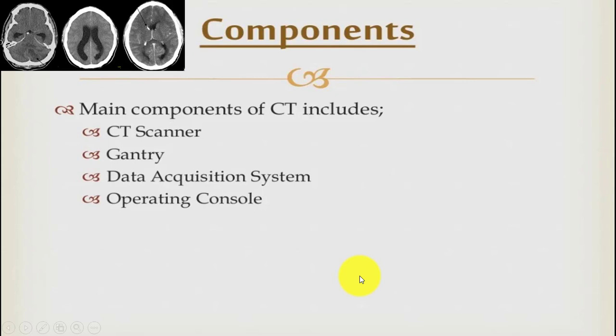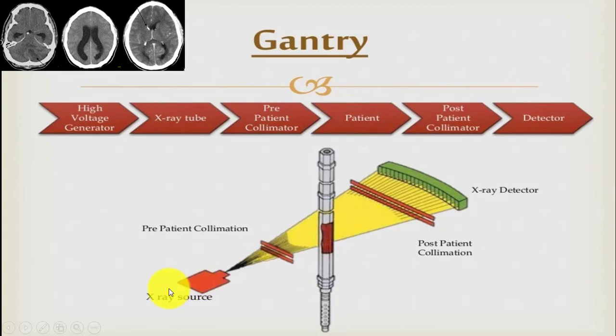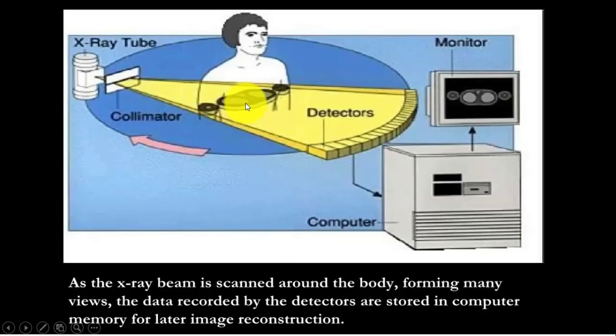In the CT scan system, high voltage generates x-rays which then pass through the x-ray tube, then pre-patient collimation, then patient scanning, then post-patient collimation, and ultimately reach the detectors. Here is a visual animation of the CT scan showing the x-ray tube, collimator, and patient. Multiple detectors collect the data, which is processed in the CPU and displayed on a monitor.